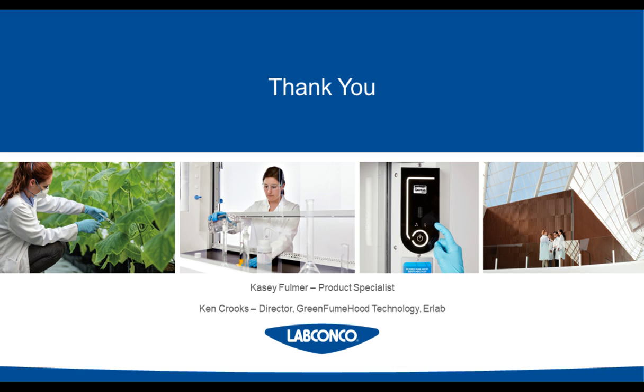That's a great question, and one that needs to be asked. So no, they do not have baffles in them, and that's actually by design. So what does a baffle do? It draws the air back away from the sash and then up. Well, that would actually load the filters in the back and risk the sensors going off before they're able to. And Ken can confirm that for me if he can.